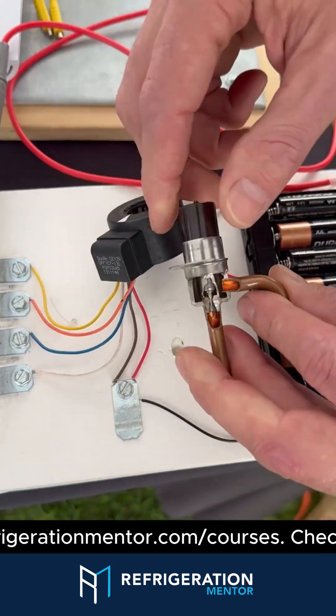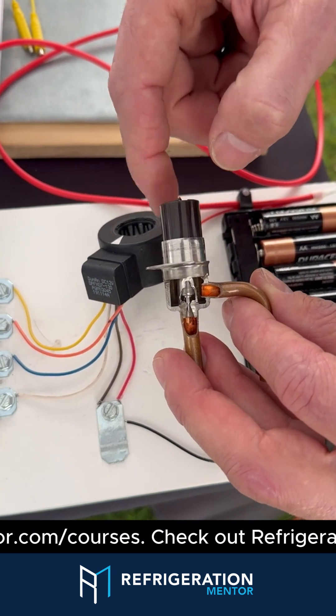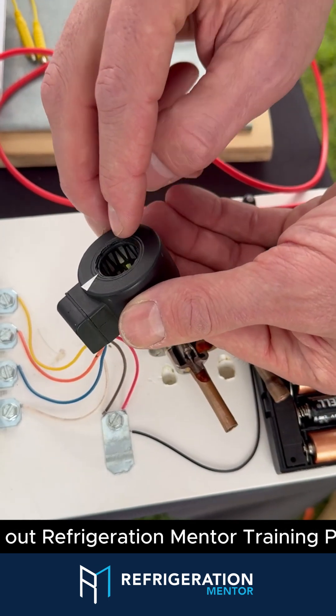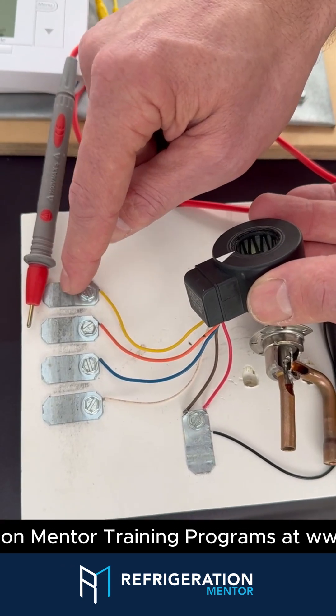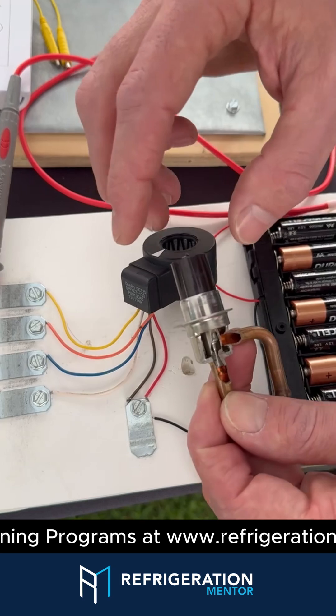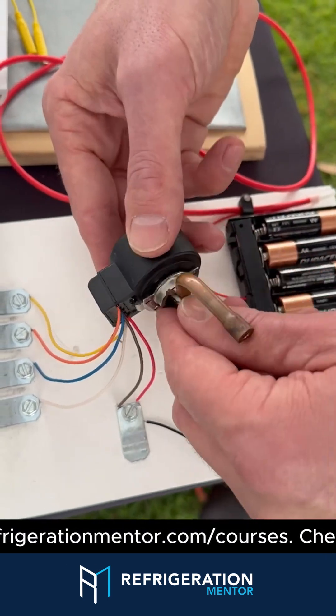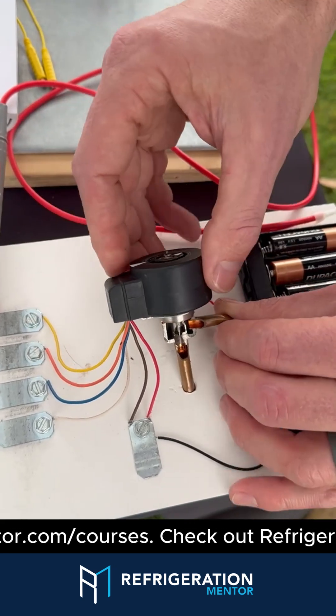Here's your little pin position right here. It takes 250 steps to go from completely closed to completely open. On the inside here, you see these teeth — there's four sets of teeth. Every time you supply a 12-volt pulse to one of these wires, you're magnetizing one set of 10 teeth. On here it looks like one magnet, but there's actually 20 poles — north-south, north-south, north-south, alternating. So what happens is you're just grabbing that magnet and making it turn.